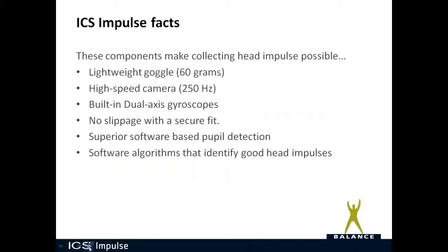There are several components that make collecting head impulses possible with this device. The first is lightweight goggles — only 60 grams — because you don't want the goggles to slip during head impulse testing. The high speed camera at 250 hertz is very important for picking up catch-up saccades. A built-in dual-axis gyroscope measures head movement. No slippage with a secure fit is very important. Superior software-based pupil detection ensures the pupil is always detected to capture catch-up saccades. And two software algorithms identify good head impulses and good data, ensuring only good data is analyzed.